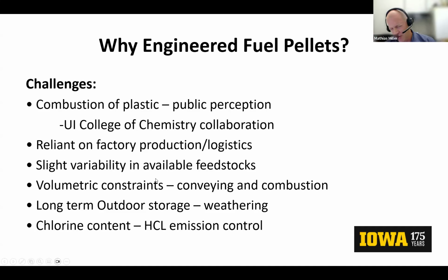Volumetric constraints: I mentioned the pellets run about 11,500 BTU per pound, similar to a lot of coal from around the country, but the BTU per cubic foot is about one third that of coal. So you'll run into volumetric constraints without big capital improvements to the boiler. For instance, our stoker boiler has certain feeders on the front designed for coal that fling it onto the grate into the furnace, and we get volumetrically limited through those because the heat content per cubic foot is less with this material.